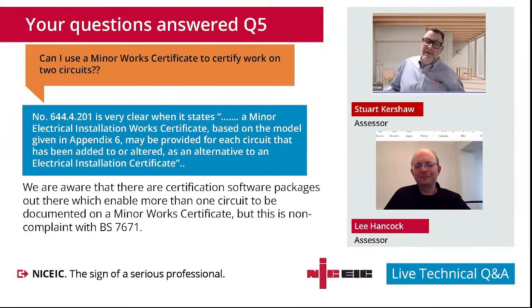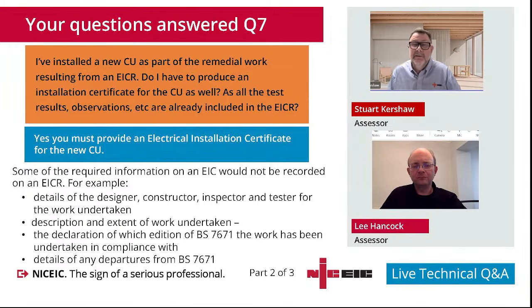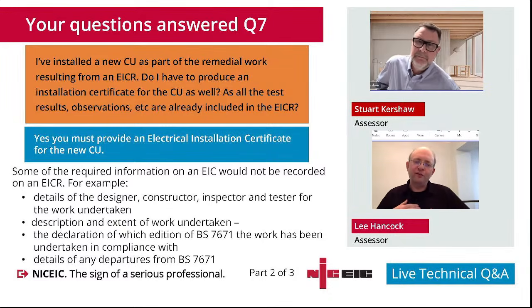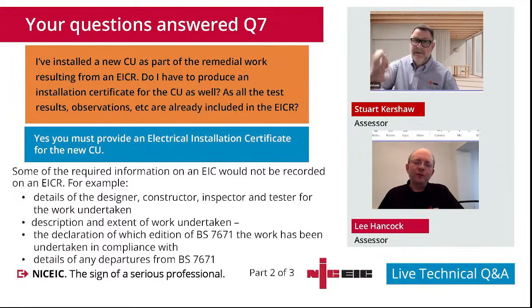No, it requires an EIC, unfortunately, due to other information that's recorded on the EIC with the design, construction, who's inspected and tested it. And again, the guidance for recipients, as Lee mentioned before, clearly states that an electrical installation certificate based on the model forms in Appendix 6 needs to be issued for the installation of a replacement of a distribution board or a consumer unit. Yeah. Again, you've selected and erected it, and you need to sign for that. Exactly. Hence the design, construction, and inspection and test. 644.1 refers. It's very clear in there.